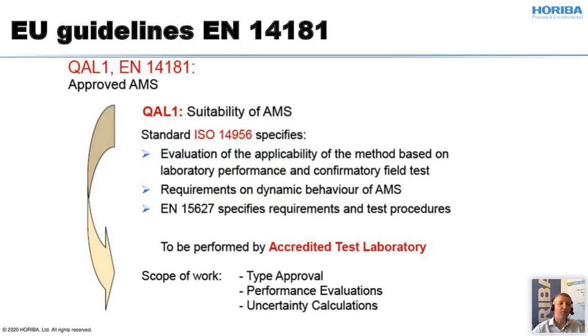In detail, we are talking about the EN 14181 guideline. You may have heard about the QAL1, 2, and 3 procedure. The QAL1 procedure is to approve the AMS. AMS is the acronym for Automatic Monitoring Systems. The QAL1 is to check the suitability of this AMS. According to standard ISO 14956, it specifies the evaluation of the applicability of the method based on laboratory performance and confirmatory field test, and requirements on dynamic behavior of this AMS. Related to this, EN 15267 specifies the requirements and test procedures. This needs to be performed by an accredited test laboratory. The full scope of work is the type approval of the full system, the performance evaluations, and to calculate the uncertainty of the full system.